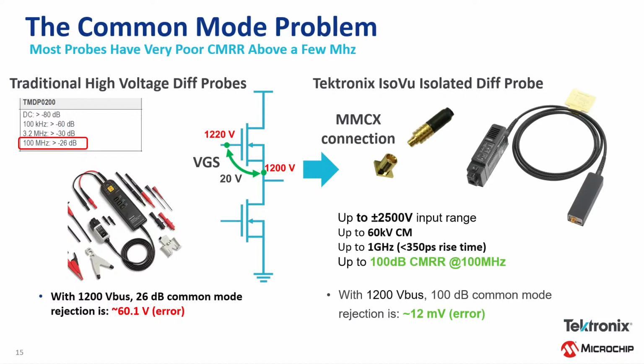What we've developed as a solution to that is an isolated differential probe that provides galvanic isolation from the probe head back to the connection on the scope. It utilizes MMCX connections down to the device, providing extra shielding and a very solid connection down to the board under test.